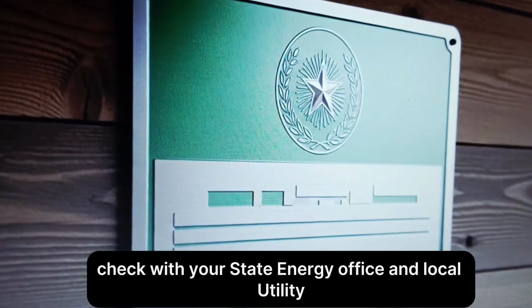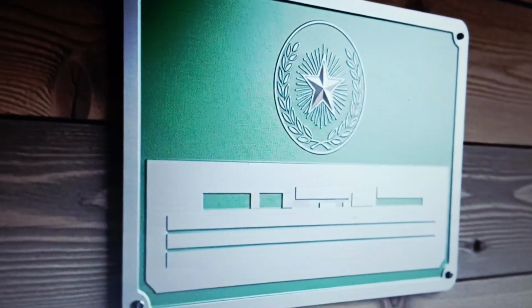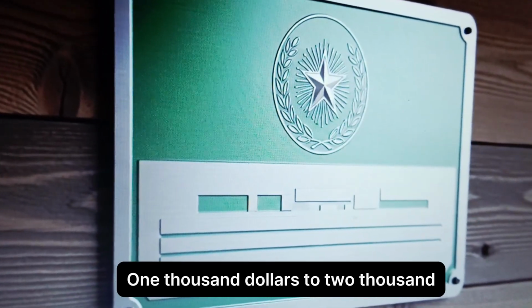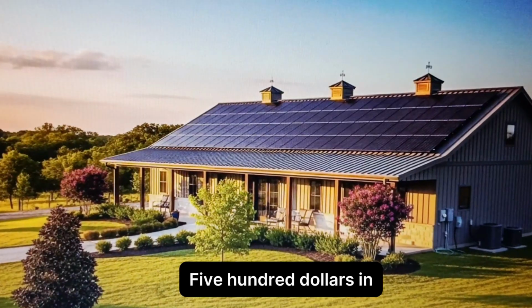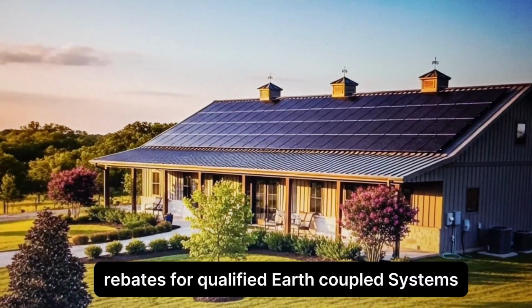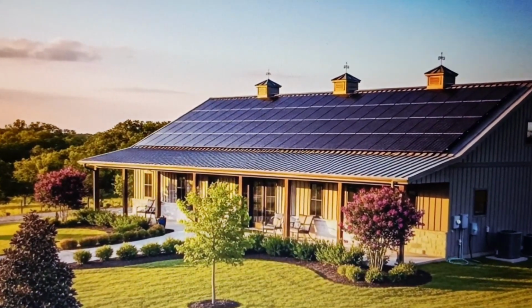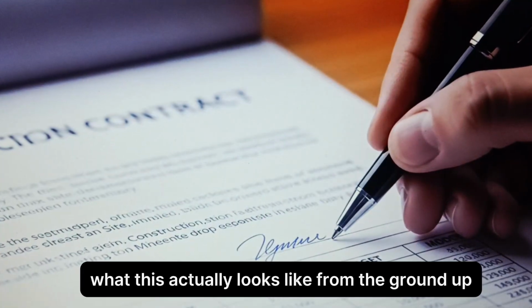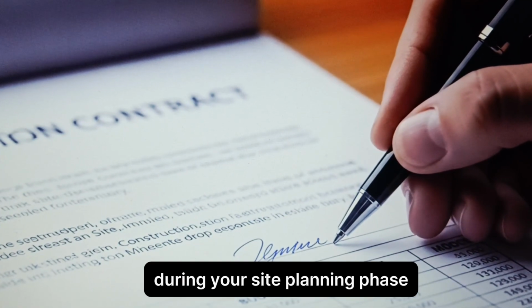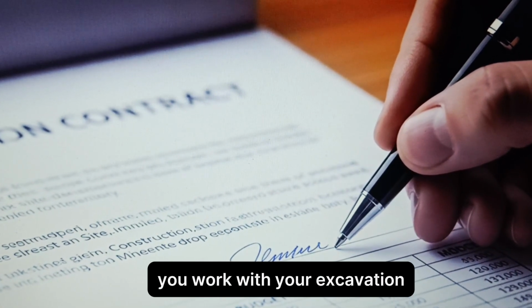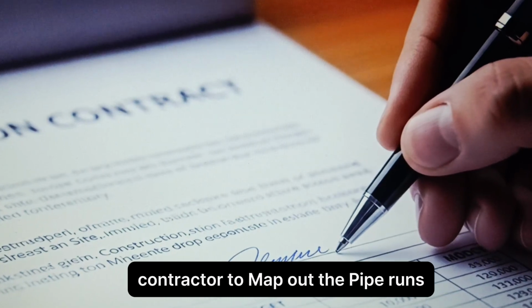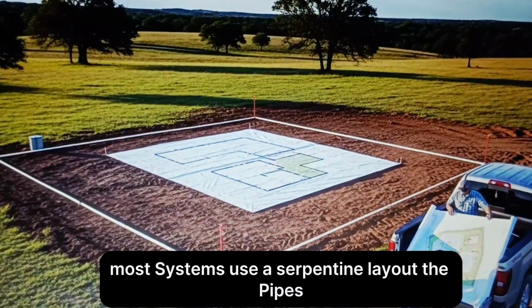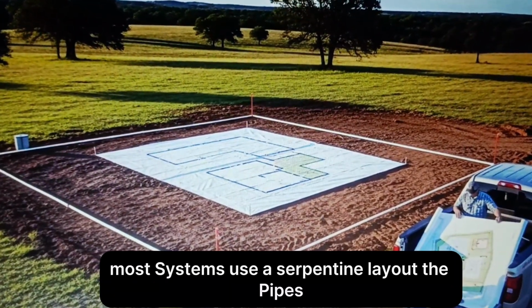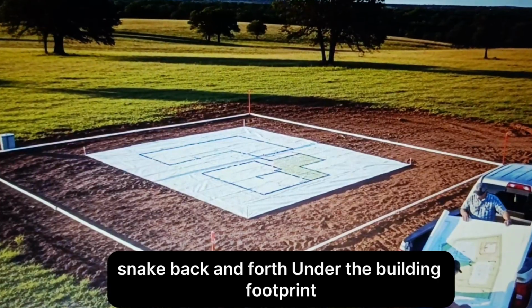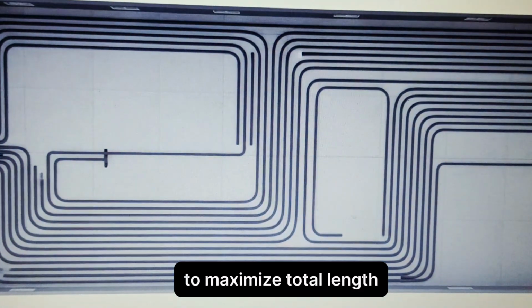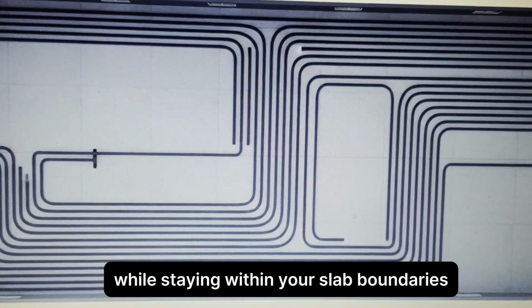Check with your state energy office and local utility. Some programs offer $1,000 to $2,500 in rebates for qualified earth-coupled systems. It doesn't hurt to ask. Let me walk you through what this actually looks like from the ground up. During your site planning phase, you work with your excavation contractor to map out the pipe runs. Most systems use a serpentine layout. The pipes snake back and forth under the building footprint to maximize total length while staying within your slab boundaries.